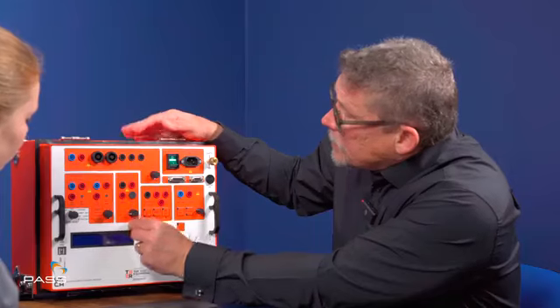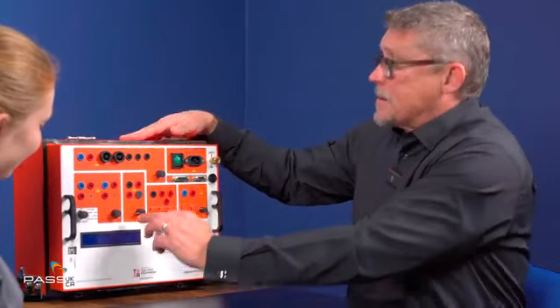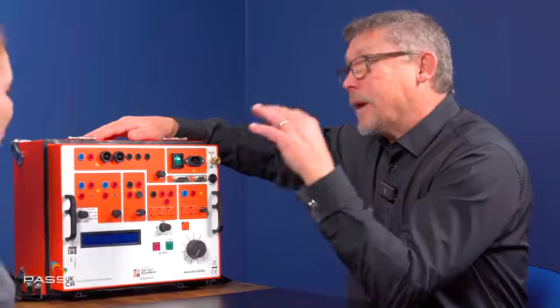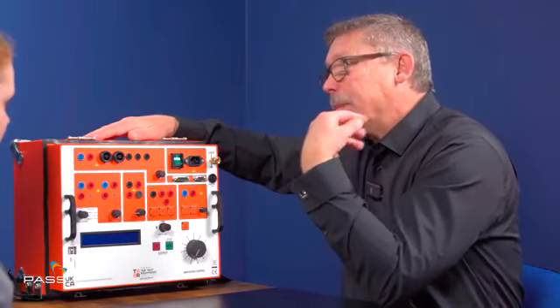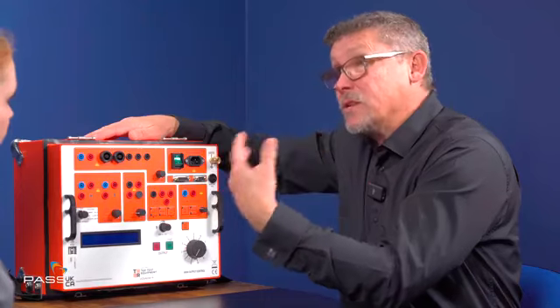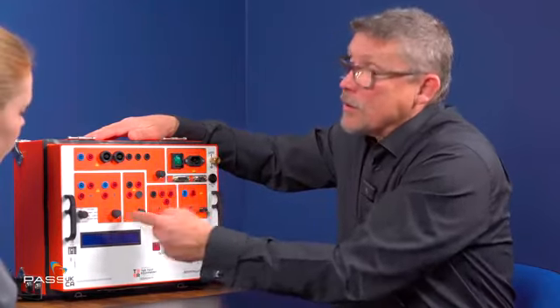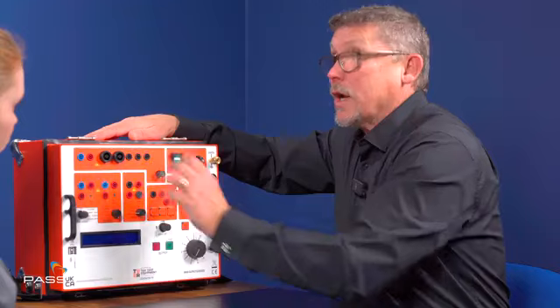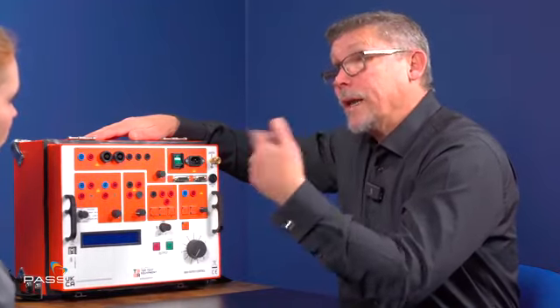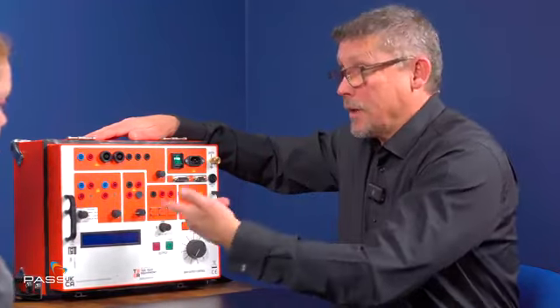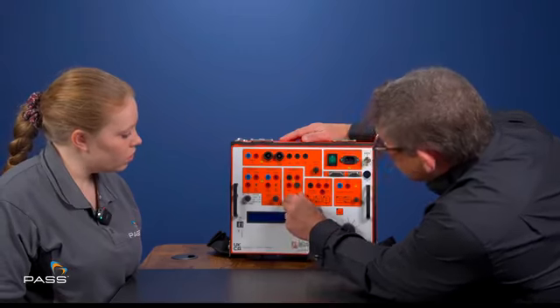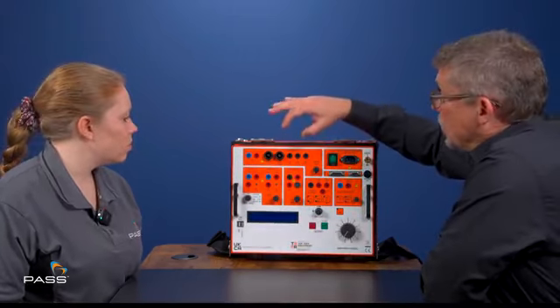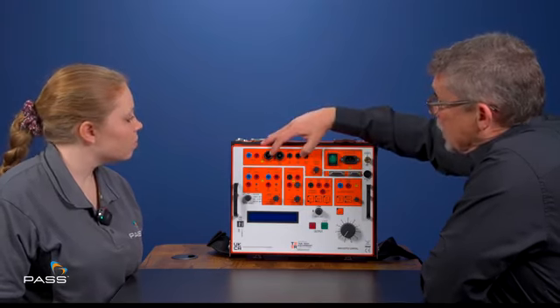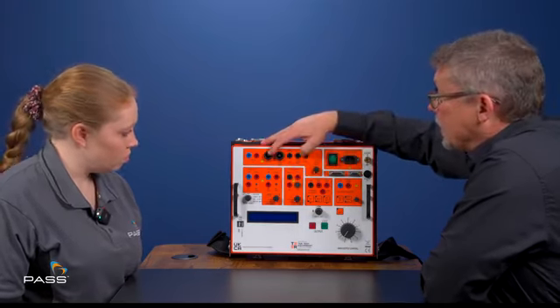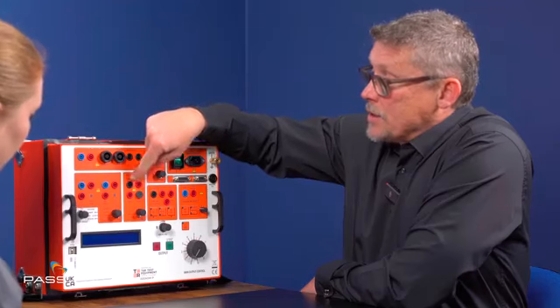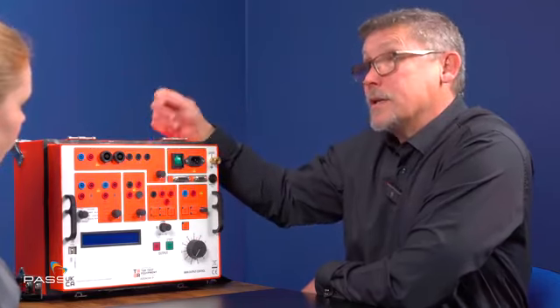We can look at it for impedance. As I said, power and impedance go hand in hand in a way. It may be that your relay's specified in terms of watts or VA, or it may be that you're testing an impedance relay, in which case we can actually show X and Y impedance and reactance in that channel there. We can use it to do CT ratio. So we can put a current from here, feed that current through the CT, put the return of the CT into here, and we can get a clear CT ratio.